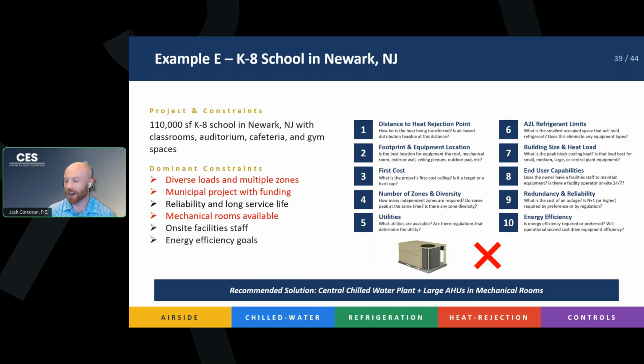Maybe it is, but you'd have to have a lot of rooftop units, right? You'd have to have a different one per zone, based on having one in heating, one in cooling, one with high latent load, one low latent load. Maybe you don't want to be running ductwork all over the place, but probably the biggest key here to switching to a different system is that there are mechanical rooms available, right? If they give us mechanical rooms, let's not take up a lot of space with ductwork. Let's use water or refrigerant and run that to our mechanical rooms where we have our units.